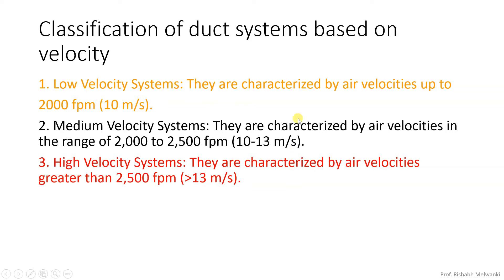Now, based on velocity, ducts are classified as low velocity, medium velocity, and high velocity. If you consider low velocity, velocities up to 2000 FPM or 10 meters per second are called low velocity systems. Velocity between 2000 to 2500 FPM, or 10 to 13 meters per second, is called medium velocity systems. The SI unit of velocity is meters per second, while IP units used by the United States — also called Imperial units — use FPM. That is why both are given here since ASHRAE is an American society that mostly follows IP units.